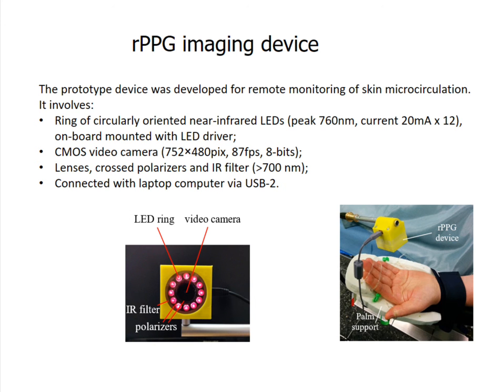The prototype device was designed for remote monitoring of skin microcirculation. It involves a near-infrared LED illuminator and video camera, both placed in a small 3D-printed case. The illuminator comprises a ring of 12 circular-oriented near-infrared LEDs connected with an LED driver. Video acquisition is performed by a board-level CMOS camera equipped with a low-distortion lens. In order to reduce skin specular reflectance, cross-oriented polarizers were placed in front of the light source and video camera. An infrared filter was placed in front of the camera to minimize the influence of ambient illumination. The rPPG device is connected to the computer USB port, which also serves as a power supply for the device.